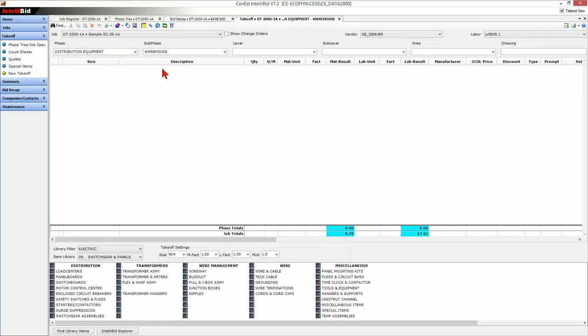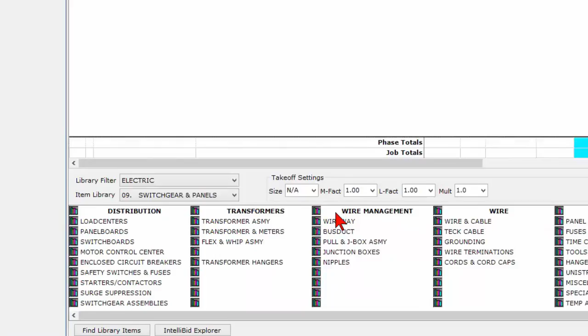Let me get the distribution set up: a 200 amp fused disconnect. I'm going to use a 600 volt NEMA 1, 200 amp - pick one of these. Now I'm also going to get a quote for the 75 kVA transformer and the 200 amp panel board, so I'm going to grab a transformer assembly that will actually add the primary and secondary winding as well.